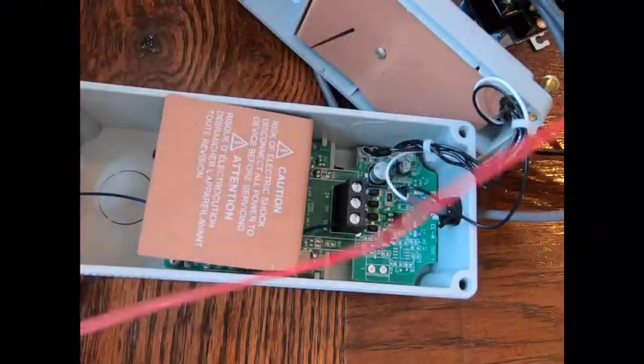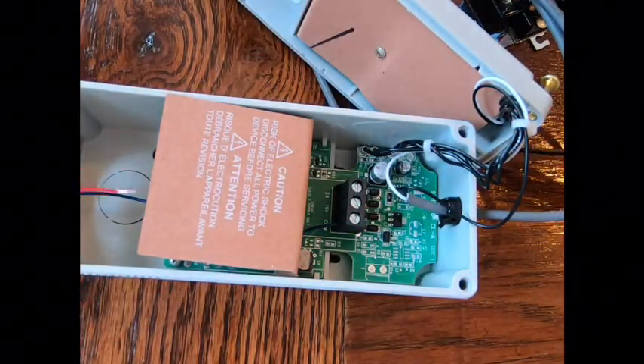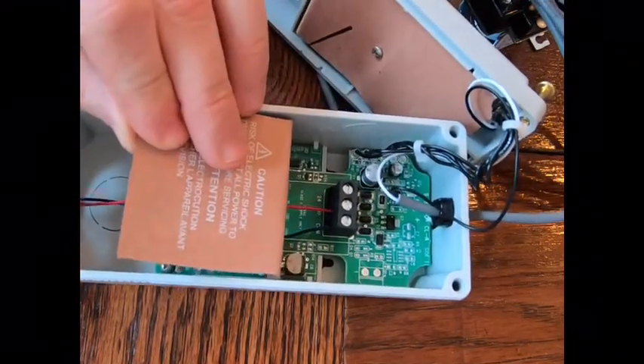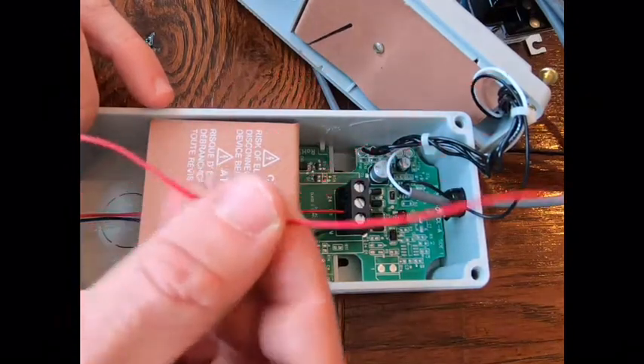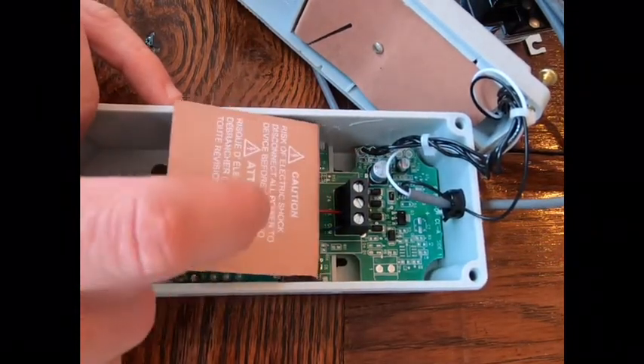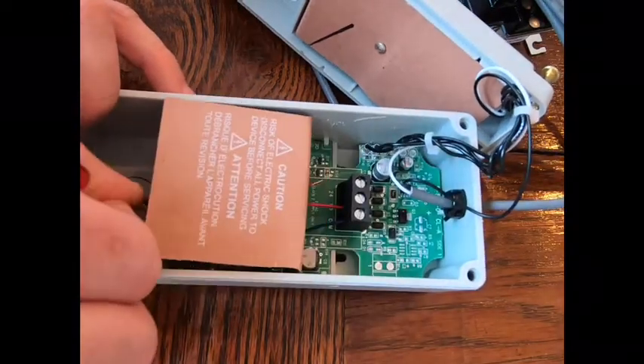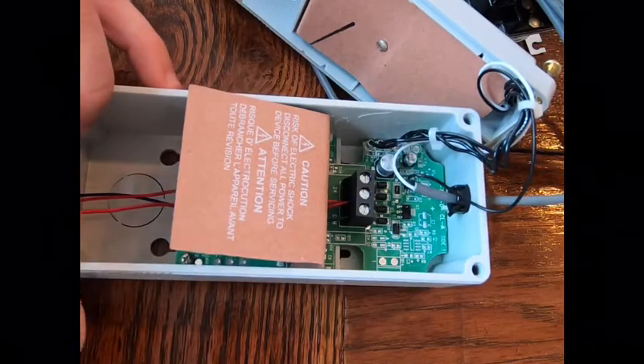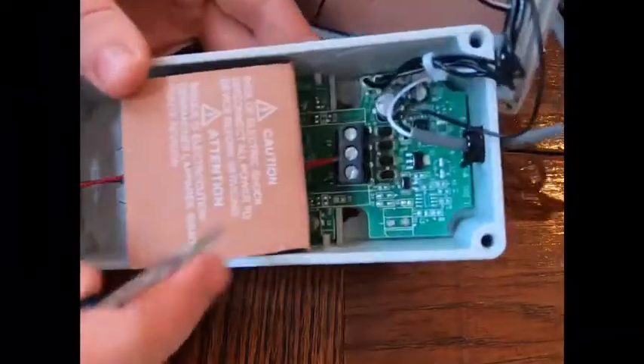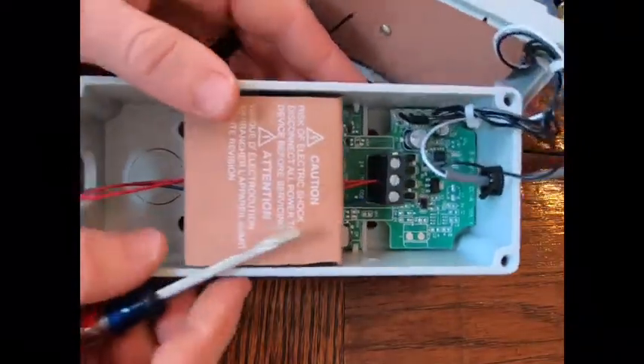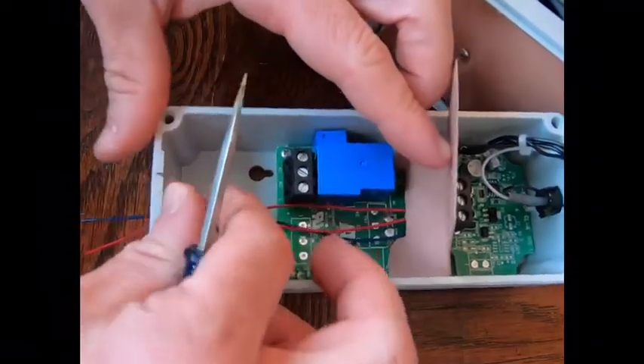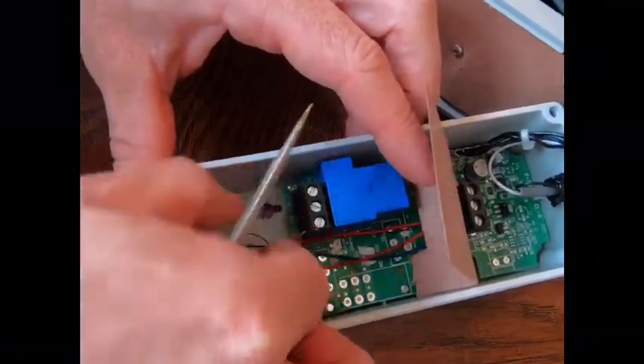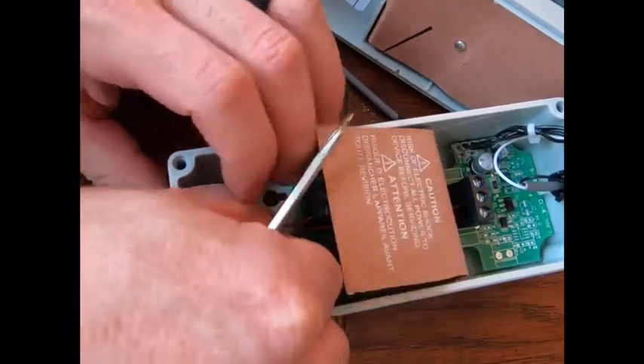All right, next we'll work on the power supply. You're going to need a piece 4 to 5 inches long with both ends stripped, and then another one that's about the same length as the blue common wire you ran already. So what you're going to do is put both the short wire and the long wire in the same connection, and unlike what I'm doing in the video, you're actually going to move it over to the left connection where the 24 is. The 24 stands for the 24 volts coming from the air handler to the Aquastat. Then you'll take the jumper wire and put that into the C, which is all the way on the right on the lower connections.